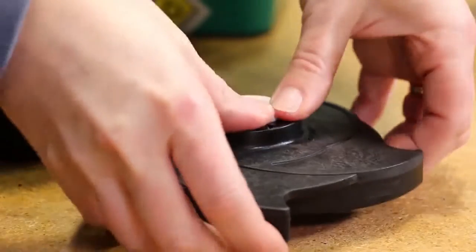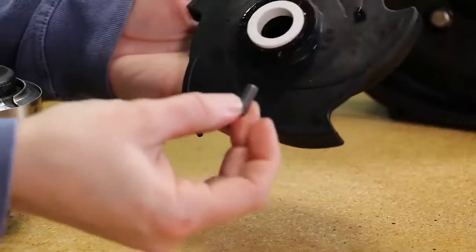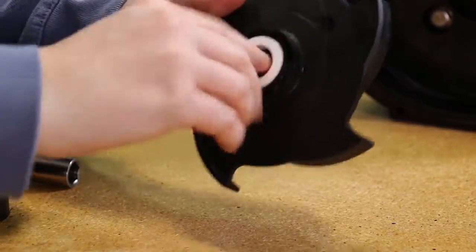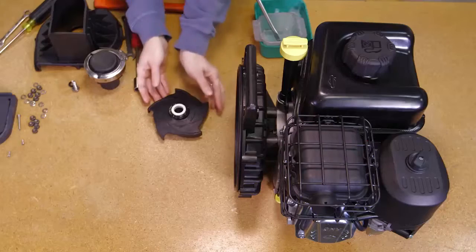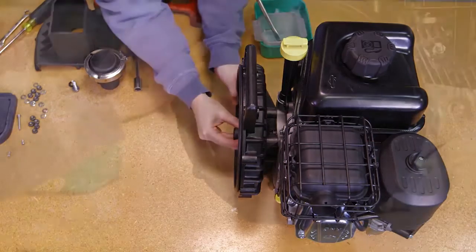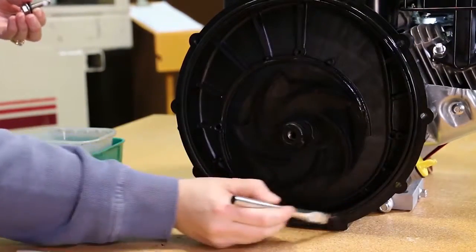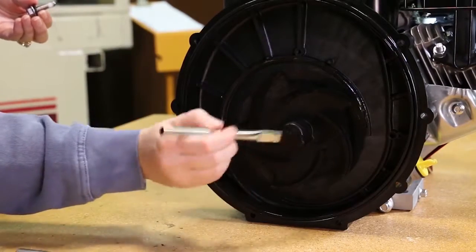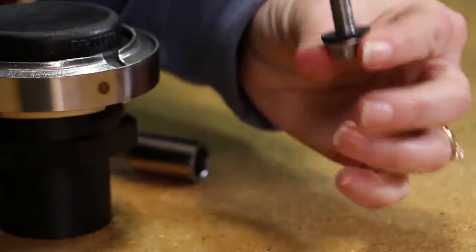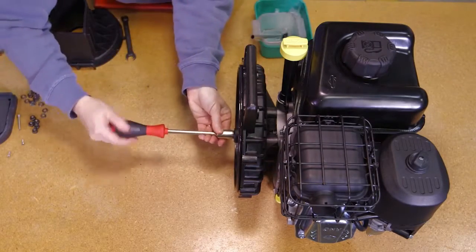Be absolutely sure that the ceramic seal half is bottomed out and installed squarely. Place the impeller key in the slot located inside the impeller snout. The impeller is now ready to be slid onto the drive unit shaft. The O-ring may be sparingly lubricated with silicone to ease installation. Secure the impeller to the drive unit shaft with the impeller bolt gasket and impeller bolt. Tighten the impeller bolt until snug.